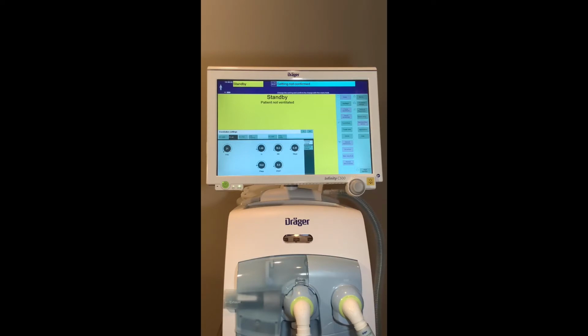On the V500, one thing to note is that your inspiratory pressure, which we call P-insp on the V500, is the inspiratory pressure that will be delivered to the patient and includes the PEEP. Therefore, when the ventilator is running, your inspiratory pressure set will match the inspiratory pressure measured.